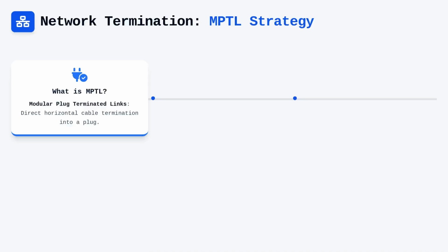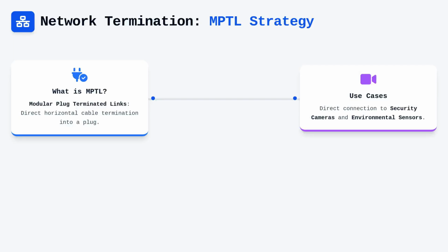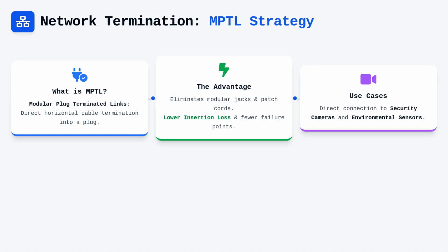In addition to cable selection, the method of termination at the work area or the device location plays a critical role in the overall health of the BAS network. Field-terminated modular plug terminated links, or MPTLs, have become a standard solution when connecting directly to devices that do not have traditional patch panel interfaces, such as security cameras or specialized environmental sensors. By terminating the horizontal cable directly into a plug, we eliminate the need for an additional modular jack and patch cord, which effectively removes a potential point of failure and reduces the overall insertion loss of the link.